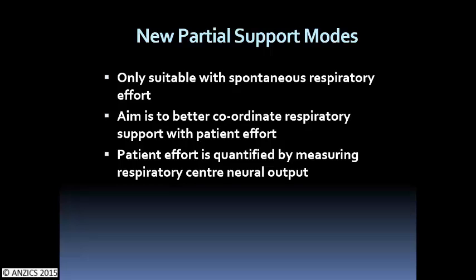If you turn the trigger right down or make it very sensitive, it self-triggers all the time. So having something that triggered off the electrical activity of the diaphragm would be perfect. There'd be no delay. As soon as it sensed that the diaphragm was starting to contract, it would initiate flow. It would terminate flow as the electrical signal dropped, and it would give support based on how big the electrical activity was. So whatever the effort you made, you got more support.